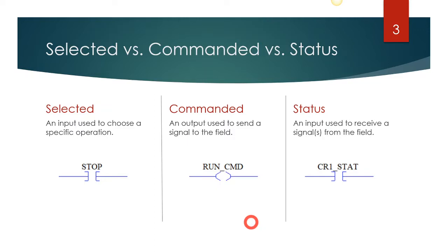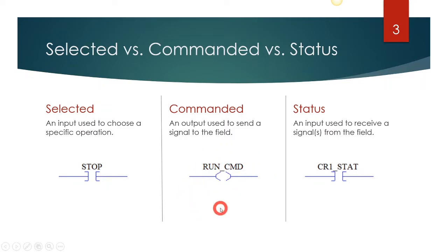A commanded output takes into account multiple items. For example, if the E-stop is not pressed, the stop is not pressed, but the forward button is pressed, then we're going to send a command out to start the motor. I have these with the address not shown because the address is not as important as what it represents. This would typically be a binary — a run command that we would use later in the program to drive a control relay, or it could literally be a control relay itself.